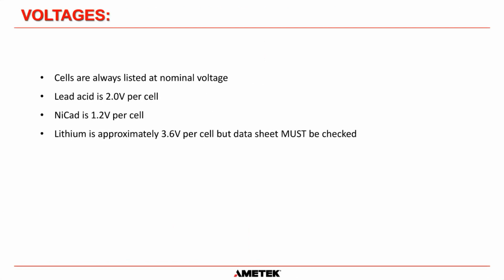So now we're going to talk about the voltages. Cells are always listed at a nominal voltage. So for a lead acid cell, the industry standard says that a lead acid nominal voltage is 2 volts per cell. Just as a side note, for a NiCad, it's 1.2 volts per cell. And for a lithium ion battery, it is approximately 3.6 volts per cell. But you must check the data sheet because it does change between manufacturer and type of lithium battery that you are working with.